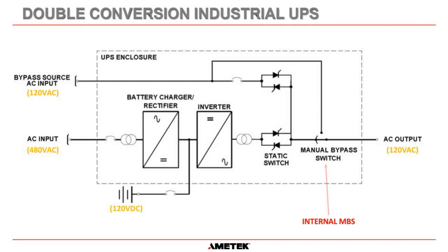What are the experiences with two-pole electronic static switches for floating systems? It's a very good question, Janet. I would have to see. You do have my email address, so if you want to send me the diagram of the system that you're talking about, then I could look into it more and get back to you. It depends on whether they're switching the neutral and what's going on. Usually with static switches, they're just switching the live on each pole. So on a floating system, it really shouldn't make a difference. I can't see why it would make a difference. But once again, I would have to see the whole system drawing to see if there's anything there that I may not be thinking about. So please send that drawing to me. It would be appreciated.